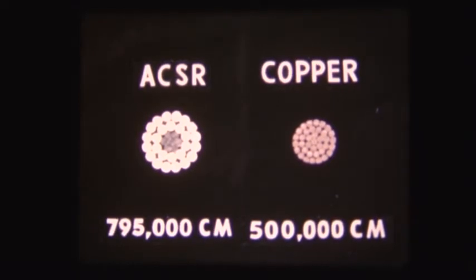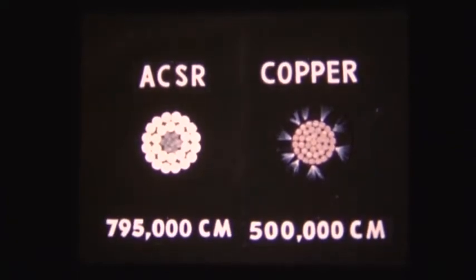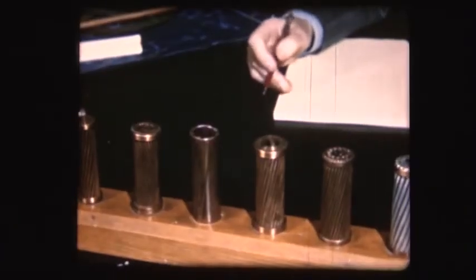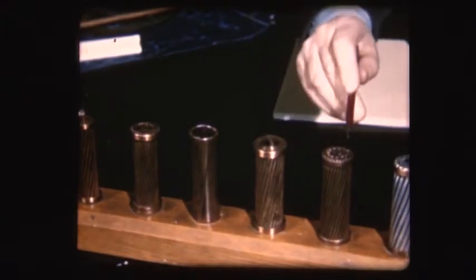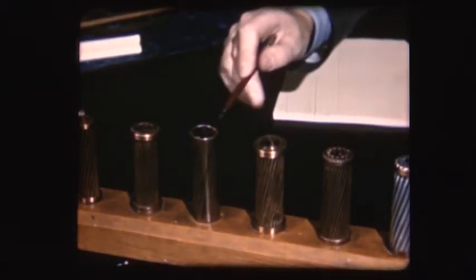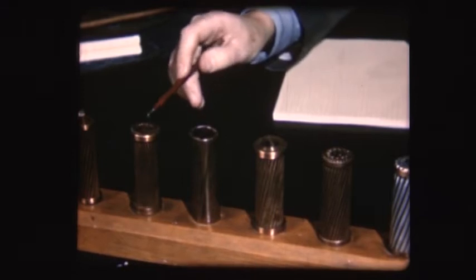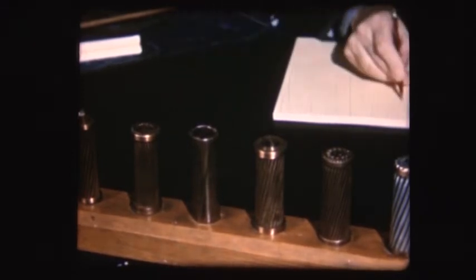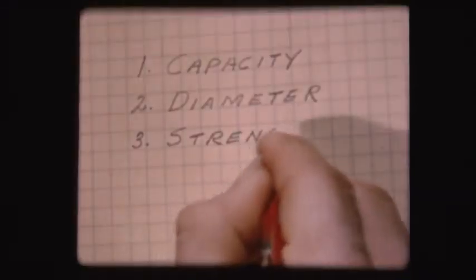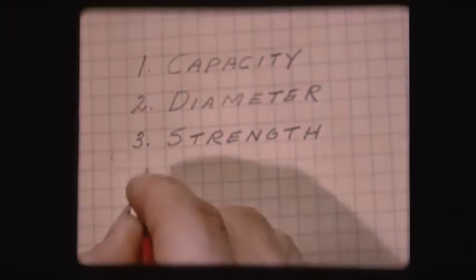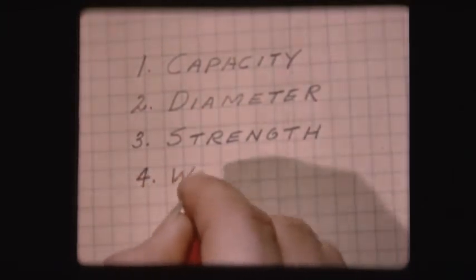The greater size of the ACSR gives it one advantage. There is less power loss due to corona, a discharge into the air that occurs at high voltage. To meet the corona problem with copper, expanded conductors have been designed. In making a choice of conductor materials, several properties, in addition to capacity and diameter, must be taken into consideration.